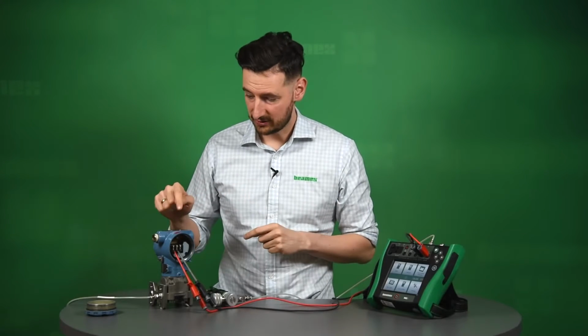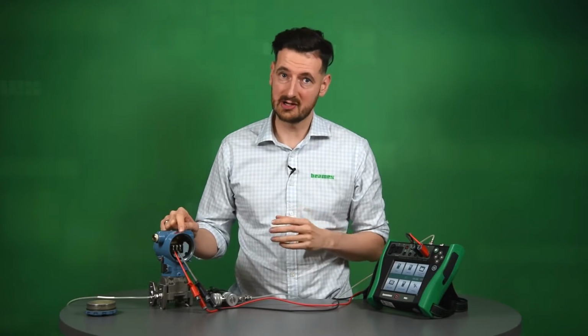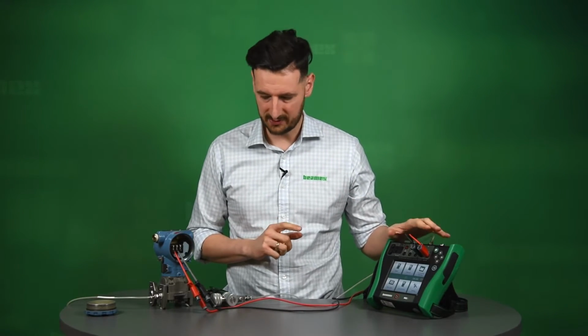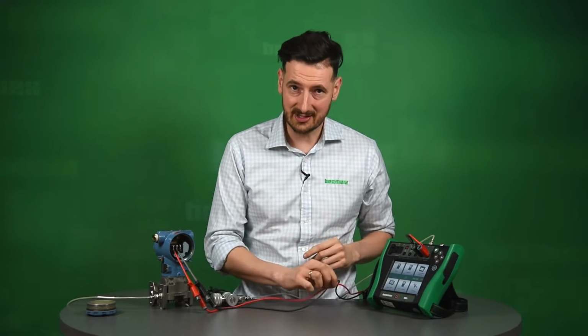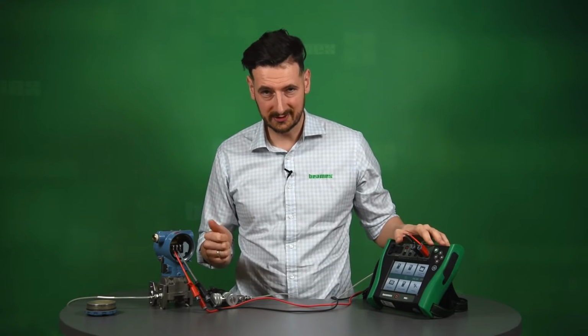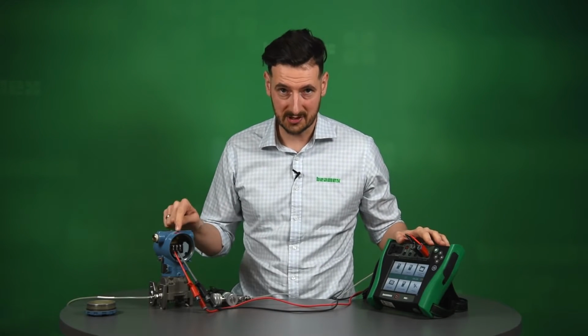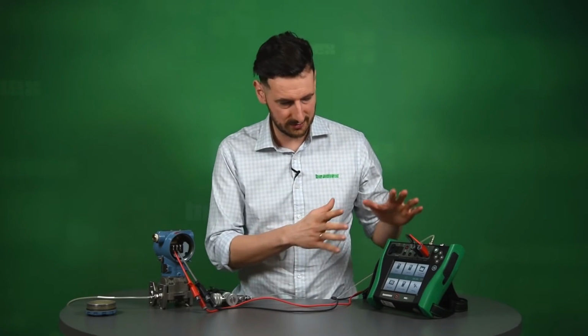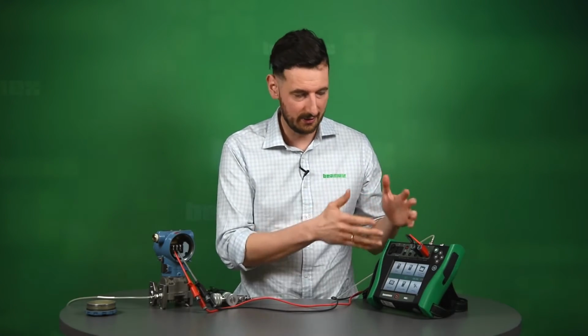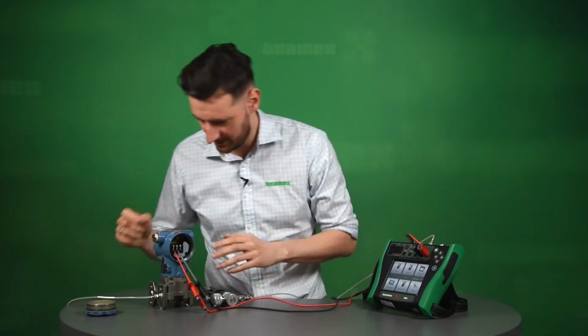We right now have connected this differential pressure transmitter to a calibrator. We're going to be using these test leads to measure 4 to 20 from the pressure transmitter back to the calibrator. We're also going to be supplying loop power from the calibrator back to the transmitter. So that's one thing. So we've got that connected here.